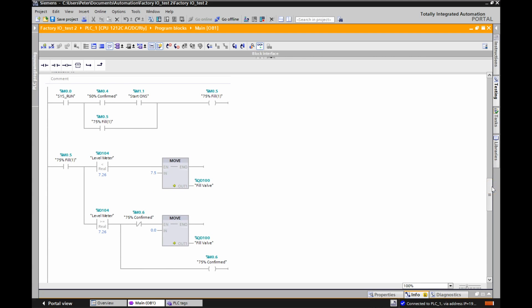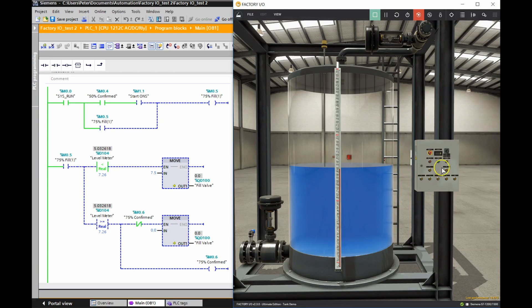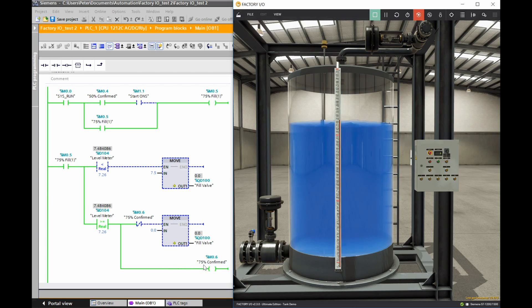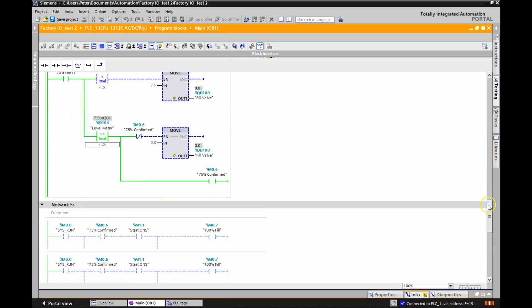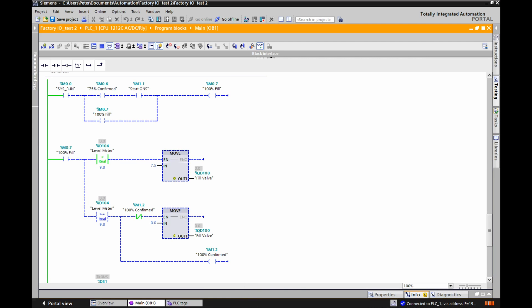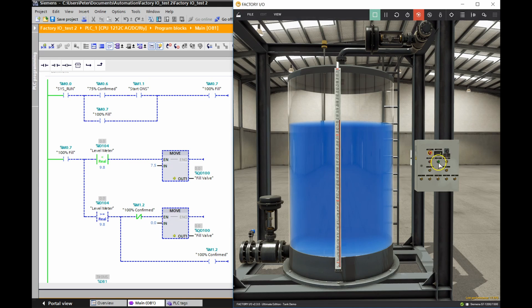The 75% section is basically a carbon copy of what we just did. Hitting the push button again, just waiting for the one shot to come through. The 75% fill instruction comes through at %M0.5, starting that portion of the circuit. Once I get to the value 7.26 it confirms I'm at 75%, which is 225 in the tank. That sets up the next portion of the circuit. You can download this PDF in the comments section - there will be a link so you can print it out and have a look.